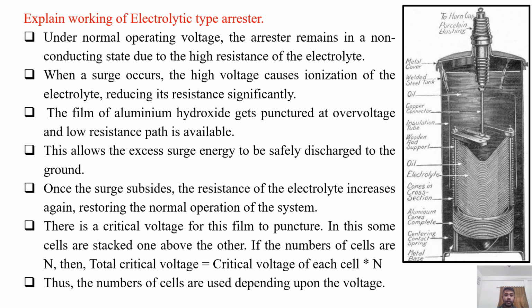Explain the working of the electrolytic type arrestor. So in the figure you can see the construction of the electrolytic type arrestor. Under normal operating voltage, the arrestor remains in a non-conducting state due to the high resistance of the electrolyte. But when a surge occurs, the high voltage causes ionization of this electrolyte, reducing its resistance significantly to a low value. The film of aluminum hydroxide gets punctured at over voltage and a low resistance path is offered. This allows the excessive energy to be safely discharged to the ground.